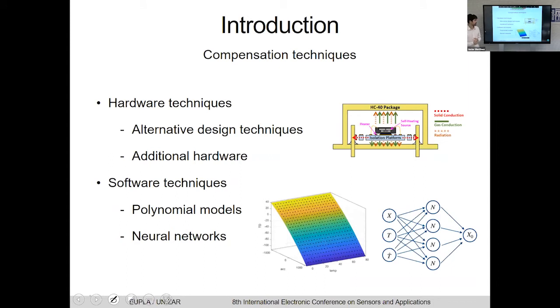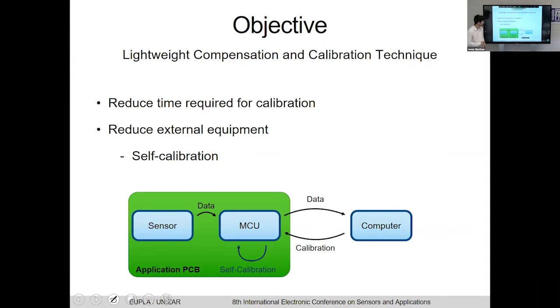There are two main ways to compensate this effect. The first one is to reduce it with hardware techniques, such as alternative design of the internal structure, or using additional hardware, like for example, adding an external package that isolates the sensor from the exterior temperature variations. The other solutions consist of using software techniques, such as polynomial models or neural networks. The problem with these techniques is that they require a lot of data to be able to fit the polynomial or to train the neural networks, and this means a lot of time in each unit that needs to be calibrated. Our objective is to propose a lightweight compensation technique that requires less time.